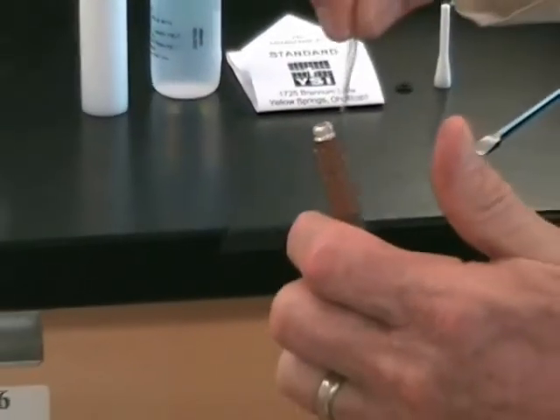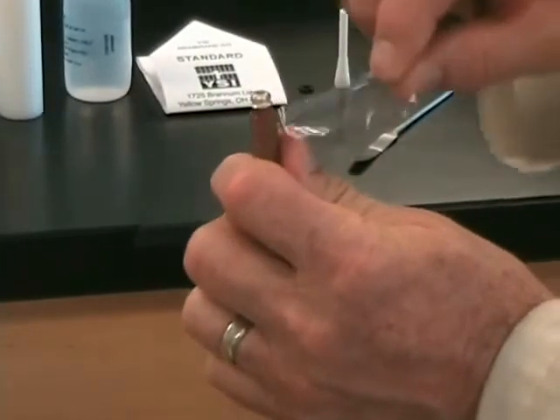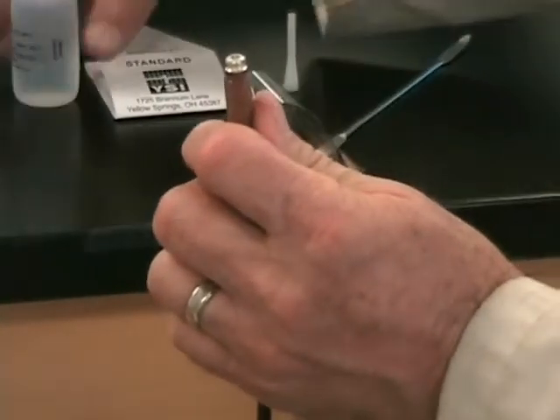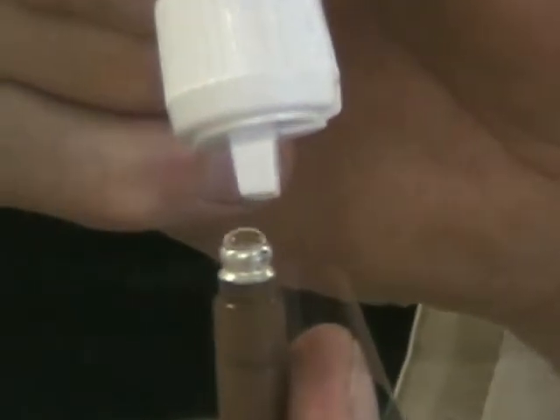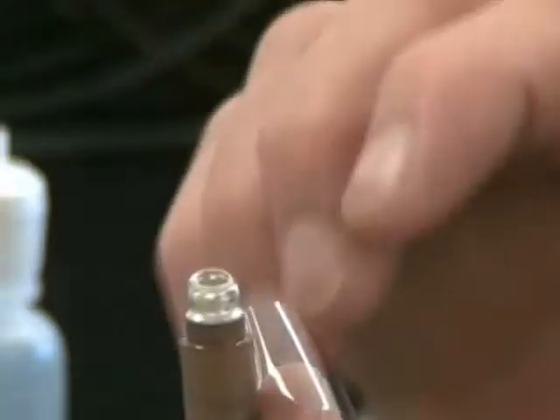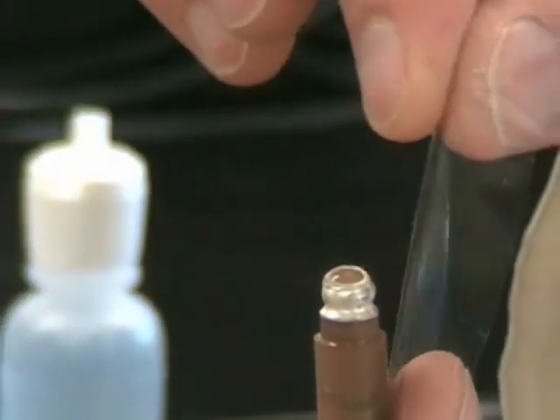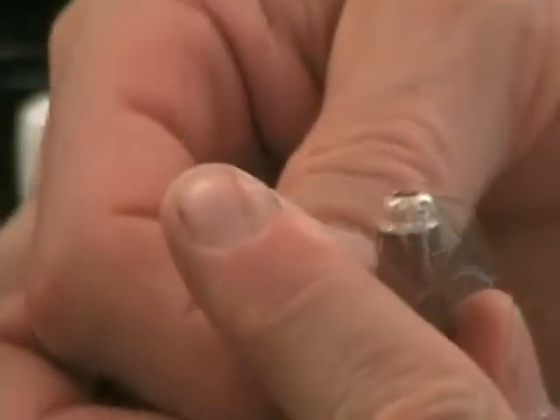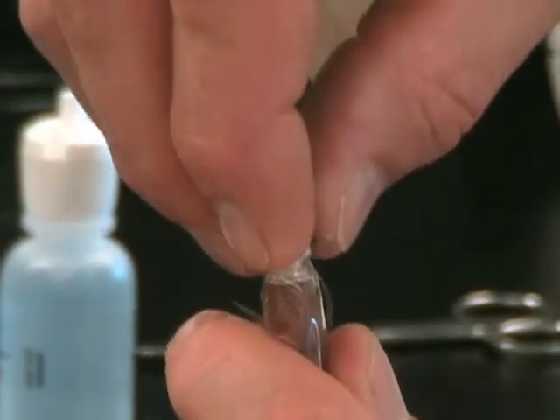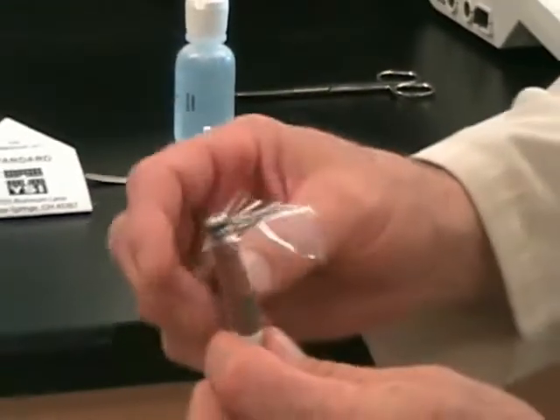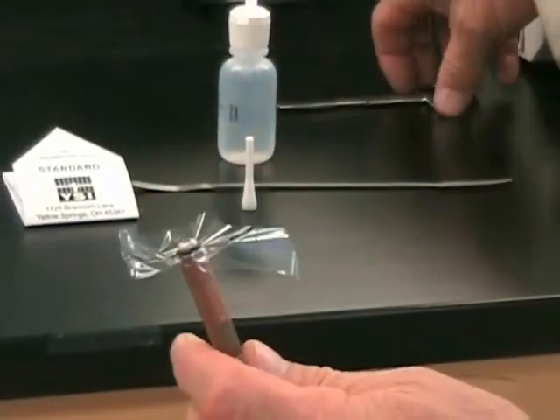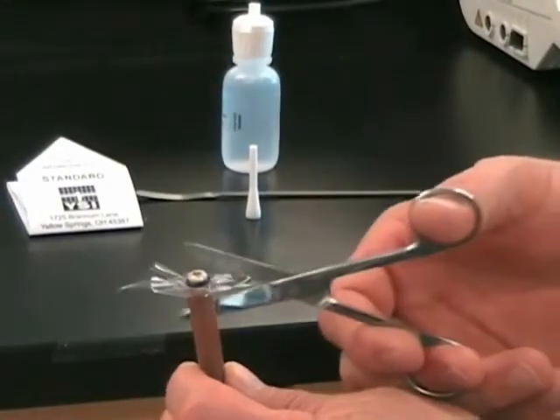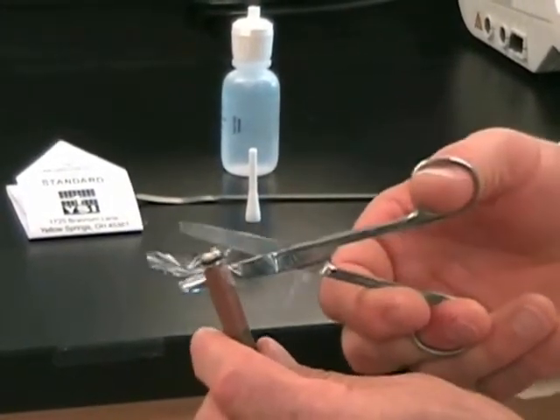So now we will adapt a membrane to the electrode, add 1 drop of KCl to form the bridge in between the silver and the platinum. Then we stretch the membrane across, capture part of the electrolyte, and then we slip on the O-ring. At this point we have a functional electrode. We need to get rid of the excess membrane.